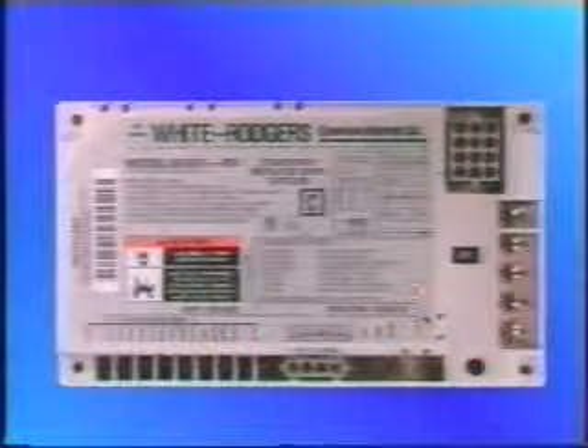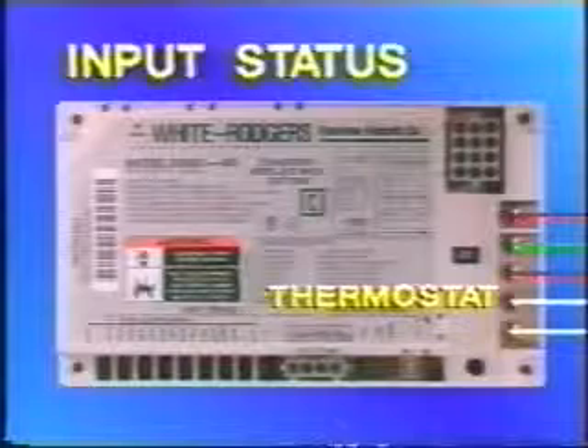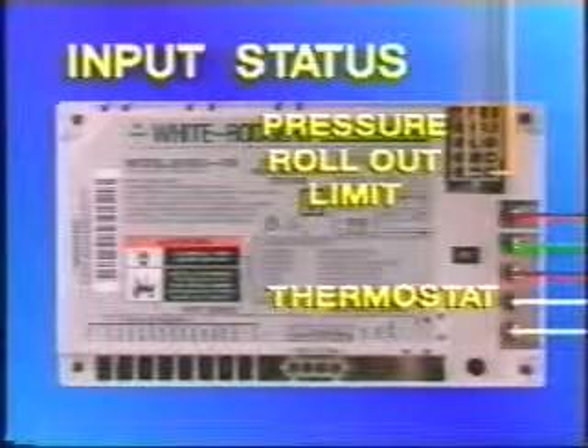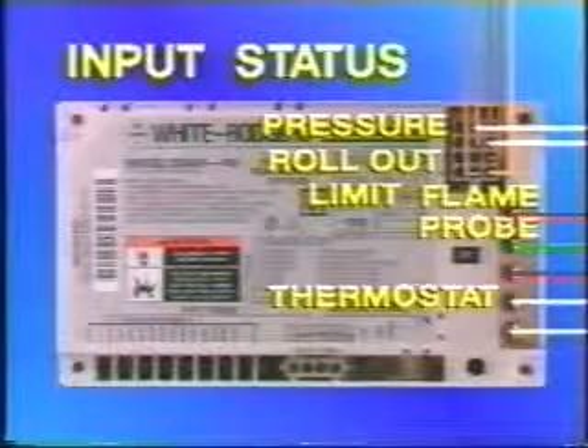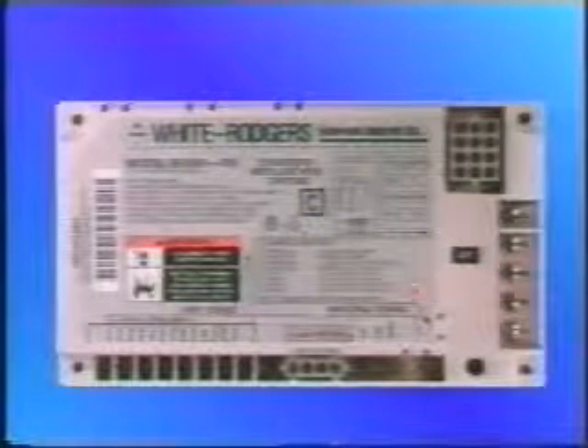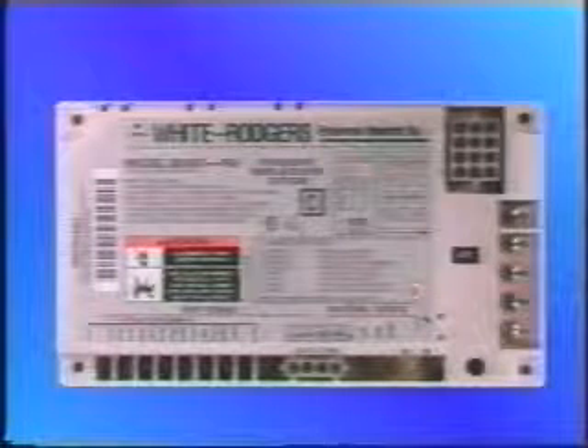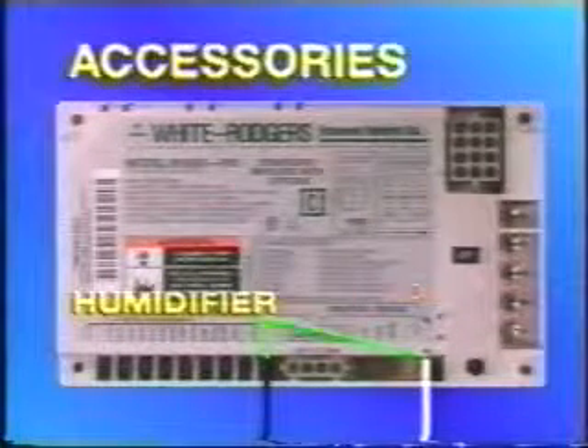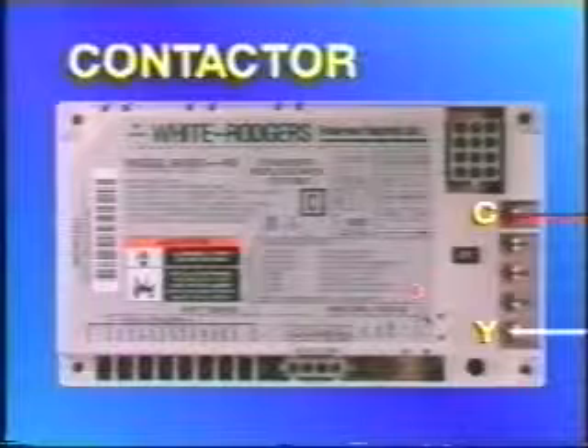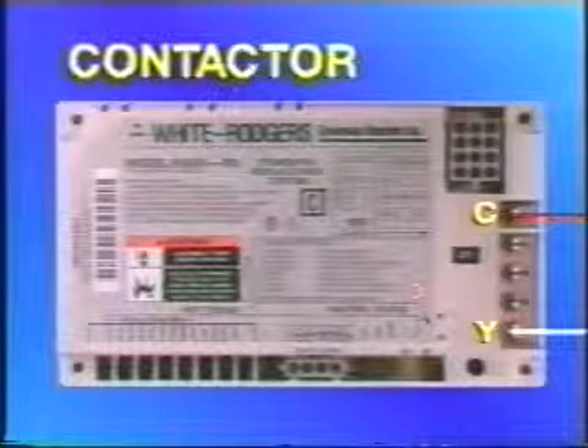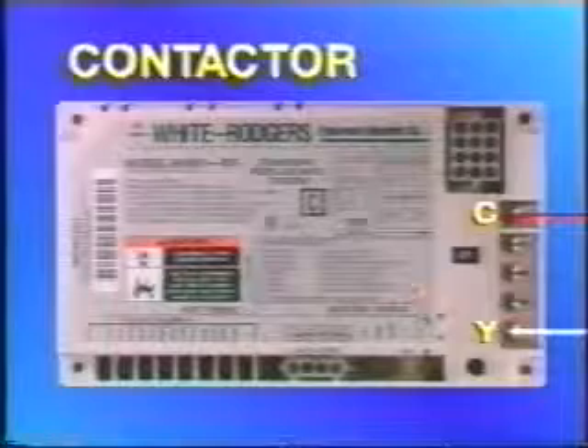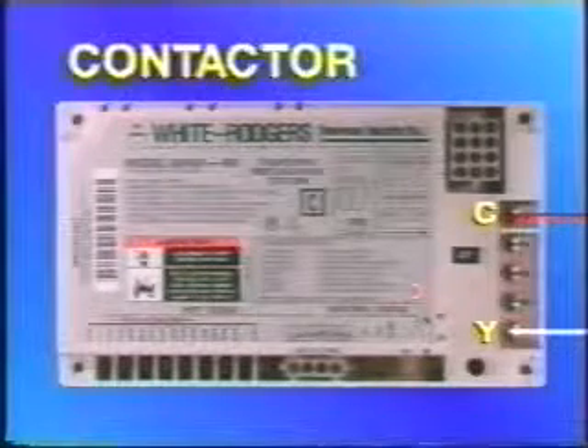There are a number of terminals that can read sensor status and switch positions. These include the room thermostat connections, pressure rollout and limit switches, and the flame sensor lead. In some versions, 2 sets of terminals control power to working accessories that are externally switched. These are an optional humidifier and an optional electronic air cleaner. The compressor contactor must be connected using the module terminals as the tie point in order to control cooling fan speed. The module does not cycle the compressor, however. Only the thermostat can cycle the compressor contactor.